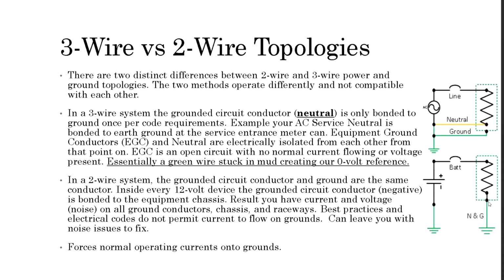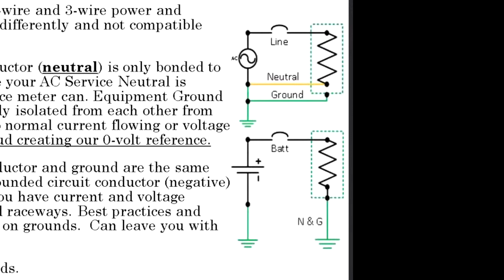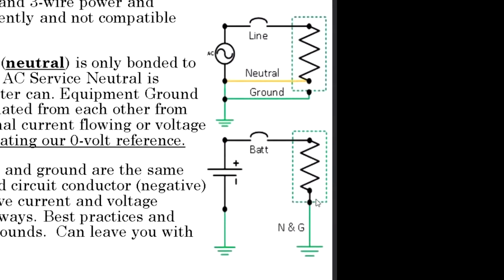Now, just contrast it and go over here and look and see what's happening here and why that can become important. All the current being supplied by the battery is also using the ground as the same conductor back to the source. So what's happening here is your zero reference point is constantly changing. Why is that? Because if we remember, we know we have an impedance between these two points. Okay, we've got current flowing through it, so that means we're incurring a voltage drop. Think about your car, even on the DC side. The DC voltages, you can lose. Same thing's going to happen with signals. So our signal reference point is constantly changing. Now, if our ground didn't have any current flowing, it's never changing.